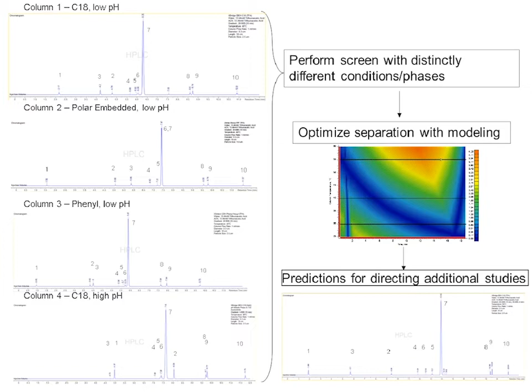I'll take a quick aside to mention the reminder that not only does one get some good information from these modeling tools around desired or predicted conditions for best operation, but one can really also understand some robustness, or likely robustness, around an analytical method with these tools. So in this particular heat map that does capture parameters such as temperature, organic strength, and gradient sensitivity, one can see in this particular case if there was a resolution or a minimum resolution that needed to be at least 1.5, then really any place in green all the way to red would be favorable. And so there may be, in this particular case, good examples where there's a broad region that is acceptable both in temperature and gradient sensitivity for developing robust conditions. And a reminder that these models are very good at predicting some actual separations if they're appropriately applied.